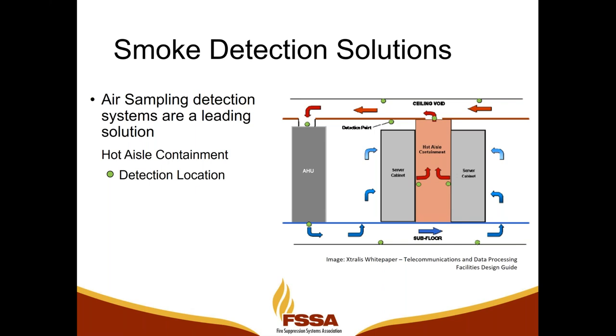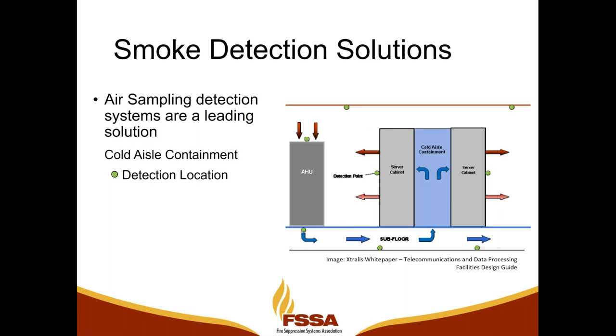For hot aisle containment systems, these green dots are places that the code basically recommends detection to be: at the ceiling for general area detection, in the ceiling plenum, at the return air unit, in the subfloor, and finally in the hot aisle containment area. For cold aisle containment, these are the locations suggested: at the ceiling, at the return air to the unit, in the subfloor, and then potentially at the server cabinet on the hot face of the cabinets.